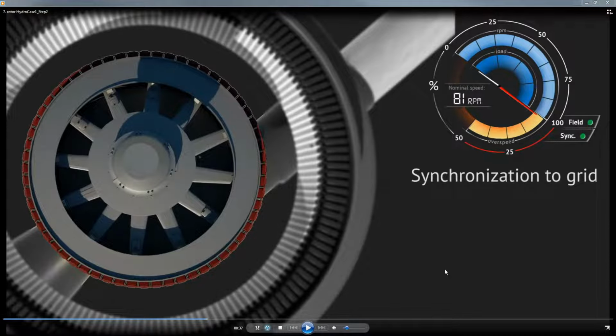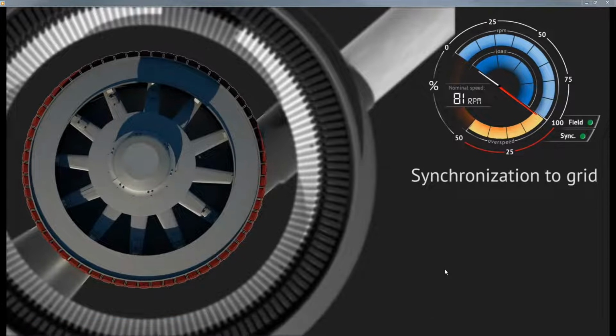Usually when we look at units, hydro generators, we will see distortions from the rotor perspective based on centrifugal forces. Therefore, as the unit increases in speed, we'll see the unit distort somewhat in some cases. And then probably the most dramatic one is when we apply the field. When the rotor is energized, that usually puts a lot of stress on the rotor and on the stator as well, but you will see some discrepancies show up. Usually when we synchronize, there's not much going on. In some cases, we wonder whether we actually missed the synchronization, or it has no impact whatsoever. And this was one of the first cases where we could see a significant impact, not when the unit was excited, but when they synchronized to the grid.